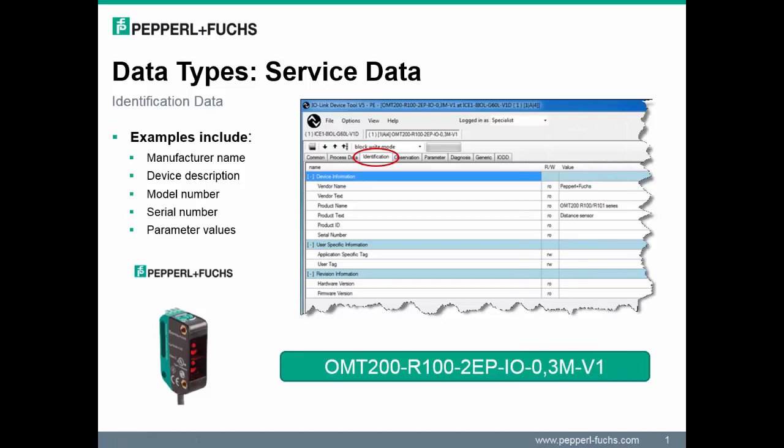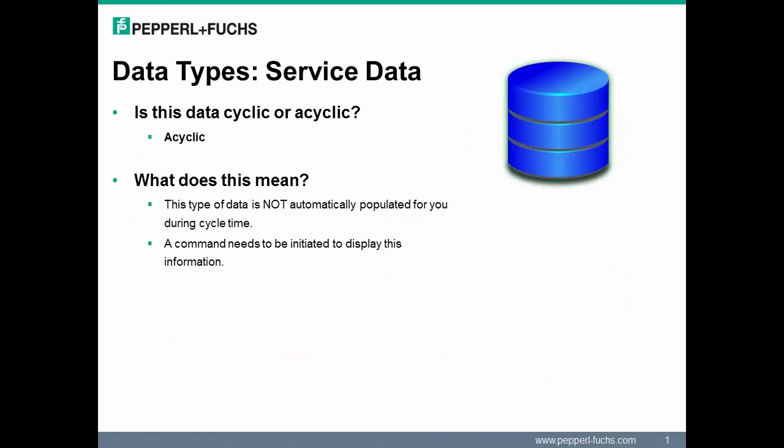Now let's move on to discussing the second type of data. Service data displays device attributes and parameters used to identify, display, or reconfigure a sensor. This slide takes a closer look at the service data of an R100 sensor connected to port 1. Service data differs from process data in that this data is acyclic — the data is not automatically populated on a cycle time. A command must be initiated in order to display this information in the PLC.